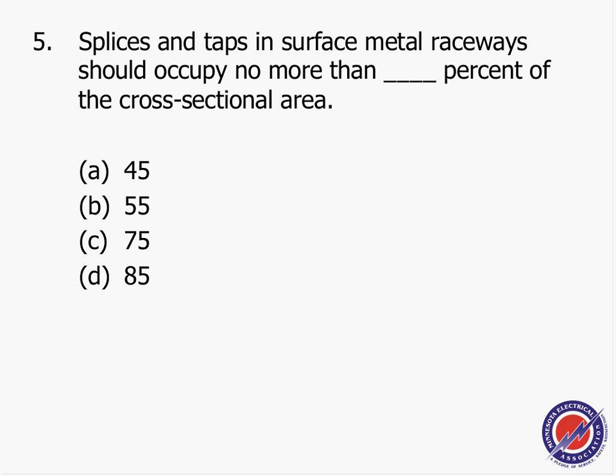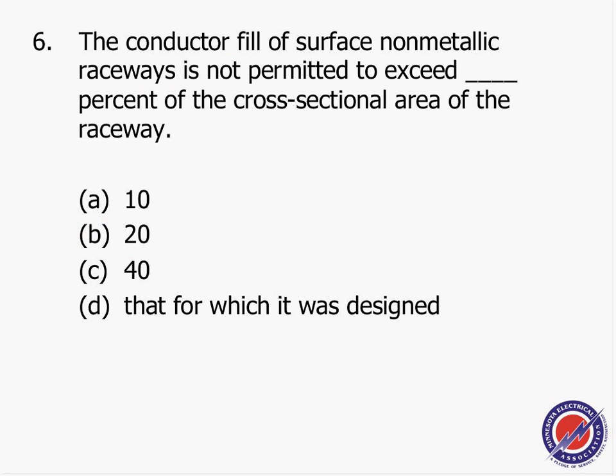Number 5. And stop me at any time. Raise your hand if I'm going too fast or too slow or something. Splice taps in surface raceways should occupy, now remember, it's splice taps and occupy, not more than. And our answer for that one was C, 75%. And that number, guys, will go with you wherever you go. In cabinets, you can't occupy more than 75% if you have splices and taps. So that's not a big deal. That was number 5. Number 6, my friend, the conductor fill of surface non-metallic.